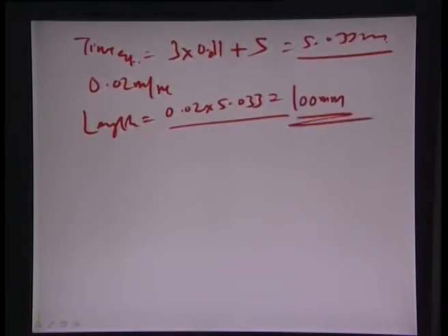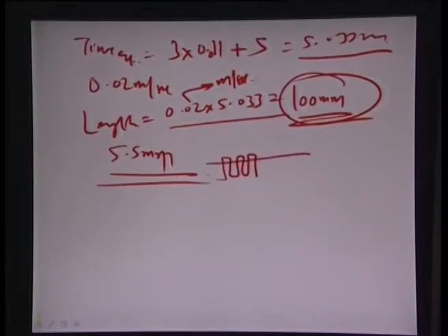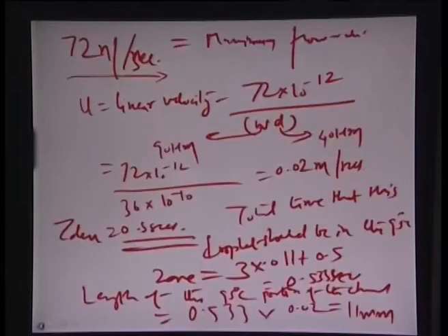Okay, assuming this was in meters per second, this is about 100 mm. So again, the very fact that you have one turn which is corresponding to about 5.5 mm, it's a design constraint that you cannot go over this in all the 3 temperature zones.